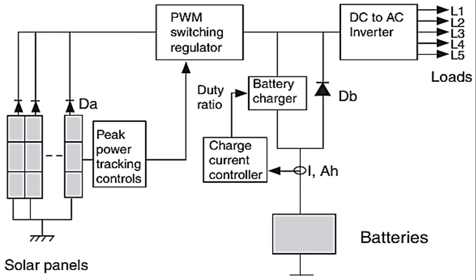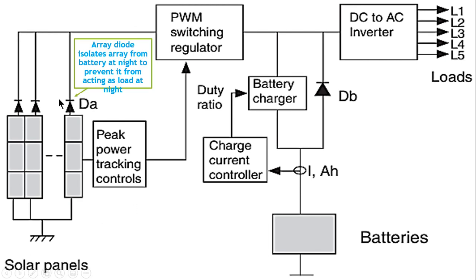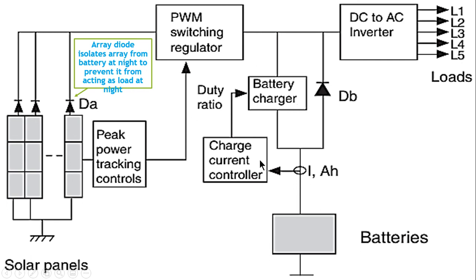Here is an example of the overall system. This is the solar panel, and these are the array diodes which isolate the array from batteries at night, preventing it from acting as a load. These diodes ensure unidirectional current flow. This is the PWM switching regulator which ensures the maximum power point tracking controller operates at optimal conditions, and this is the DC to AC converter which supplies the connected loads.